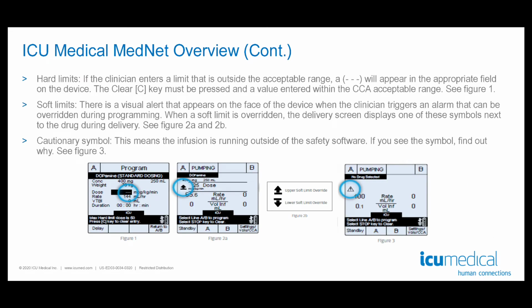When you hit a hard limit, you will see 3 dashes. You must clear this field before being able to continue to program the pump. Please see the bottom left picture that illustrates this. For soft limits, you will see an up or down arrow displayed indicating that you are operating outside of the soft limit.